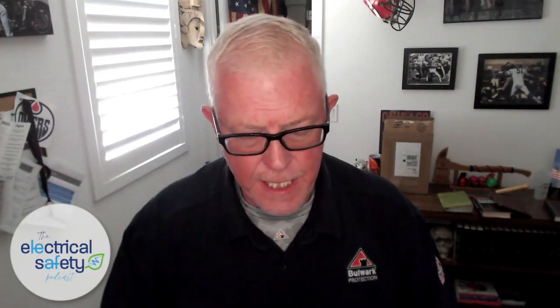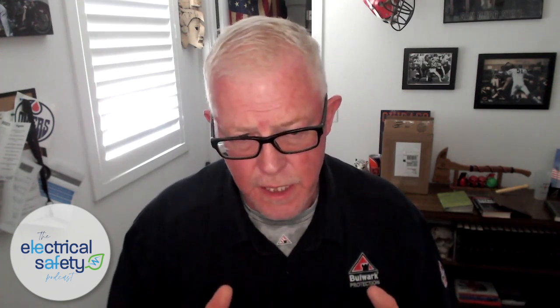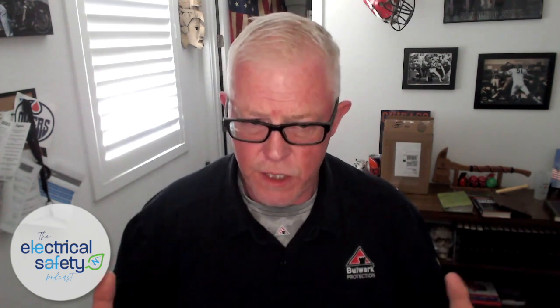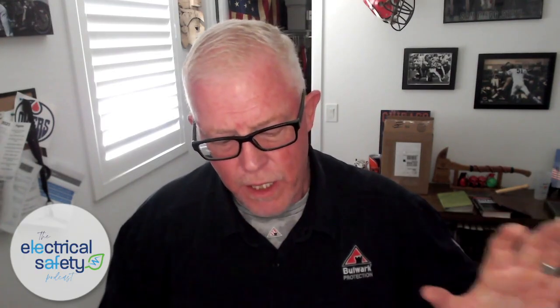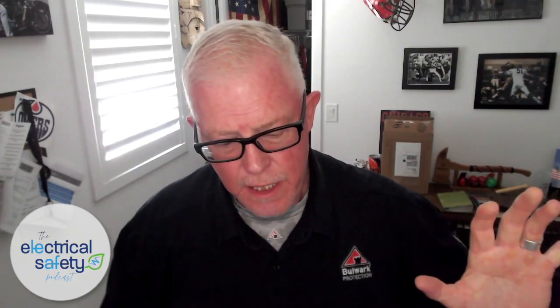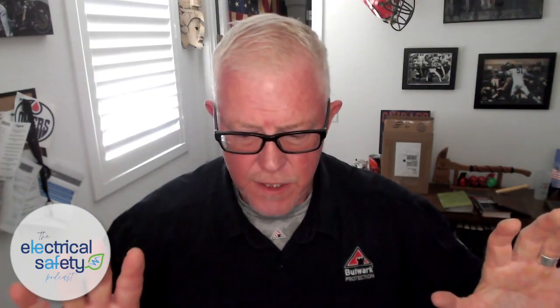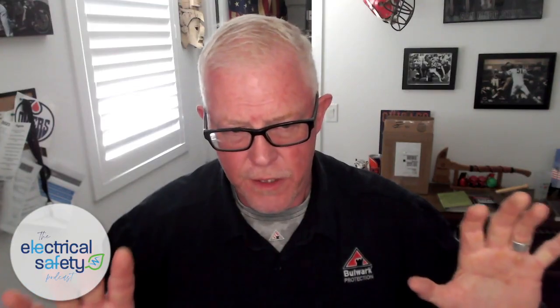At the end of the day, what we see is, yes, you will be hurt a little bit more. How much more, we don't categorically know. The arc-rated clothing technically will still work, but it'll start to reach its failure point. All we can say is that any arc-rated clothing at any ATPV or E sub BT in front of incident energy is going to be a better result than if it wasn't.